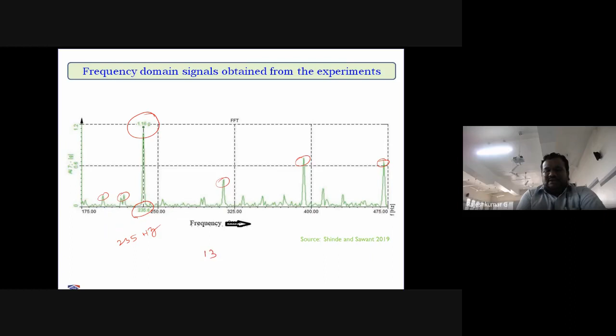13,650 RPM. So what does it mean? Here we get the natural frequency as 235 Hz in the previous curve, and then the forcing frequency or harmonic frequency as 235 Hz in this frequency domain signal, and the shaft is running at 13,650 RPM. So what does it mean? This 13,650 is the critical speed of this shaft. Therefore we should not run the shaft beyond this limit.